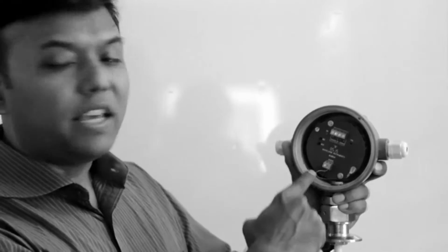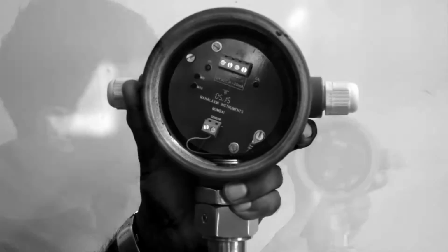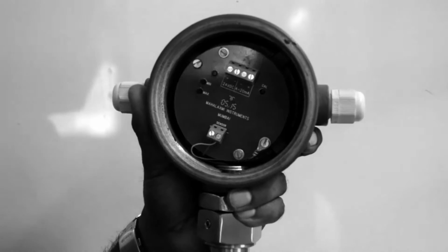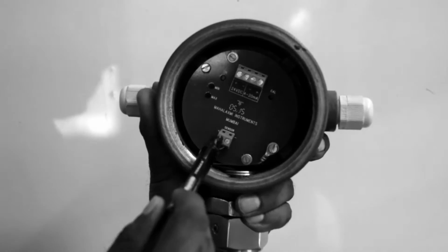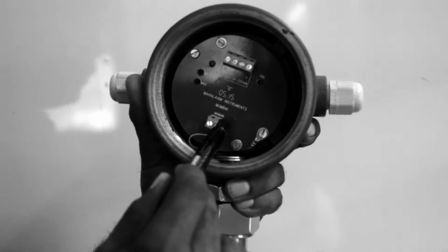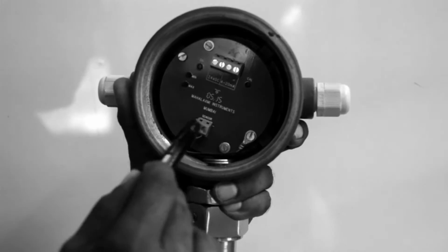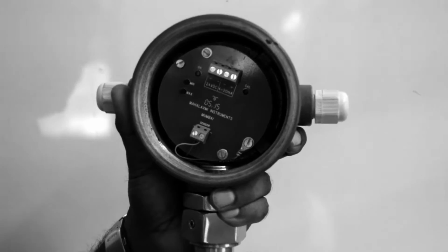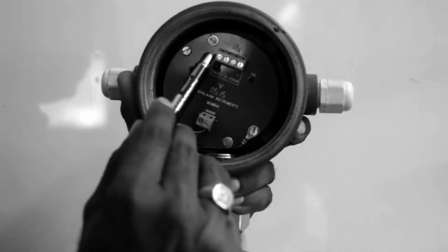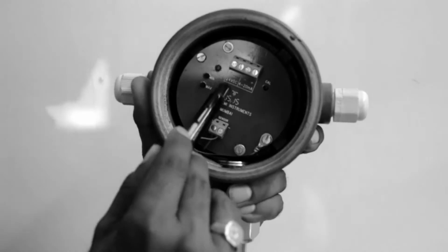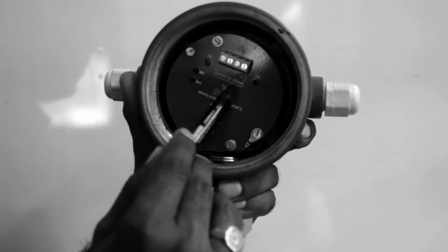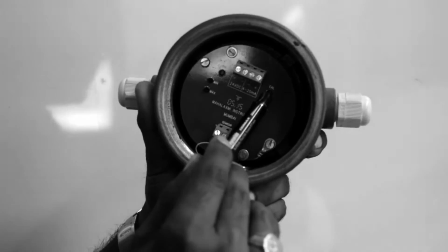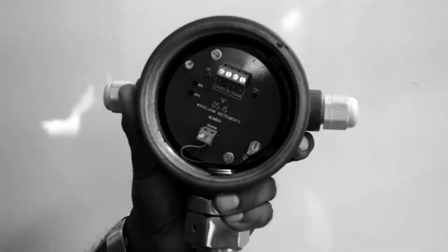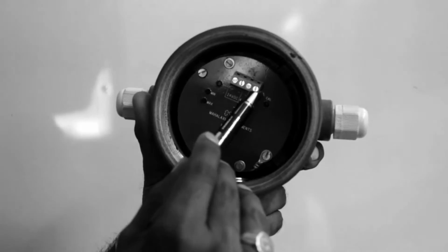today. You can see this is the electronic card of the capacitance level transmitter, and as you can see there are totally 6 terminals, 4 on the top, 2 on the bottom. The bottom 2 are connected to the inner and outer electrode of our transmitter, and the top 4 is plus 24 volts minus and 4 to 20 minus and plus. So totally 4 terminals. Both the negatives are internally short.